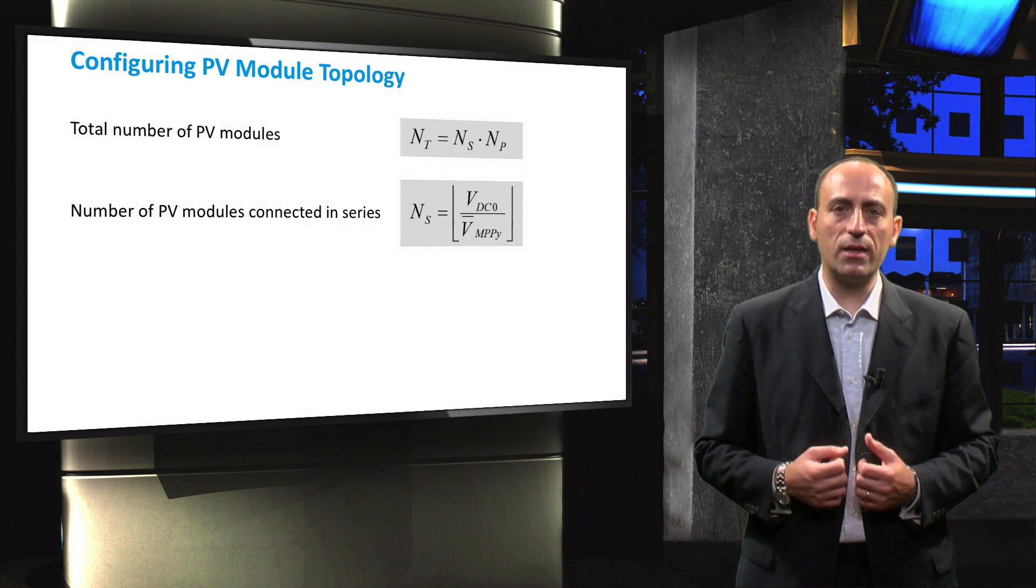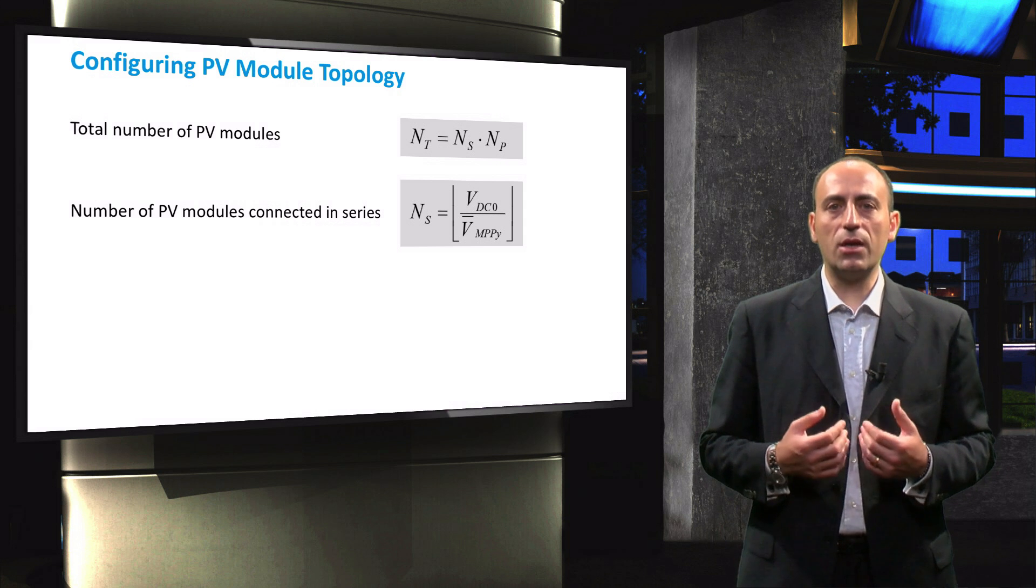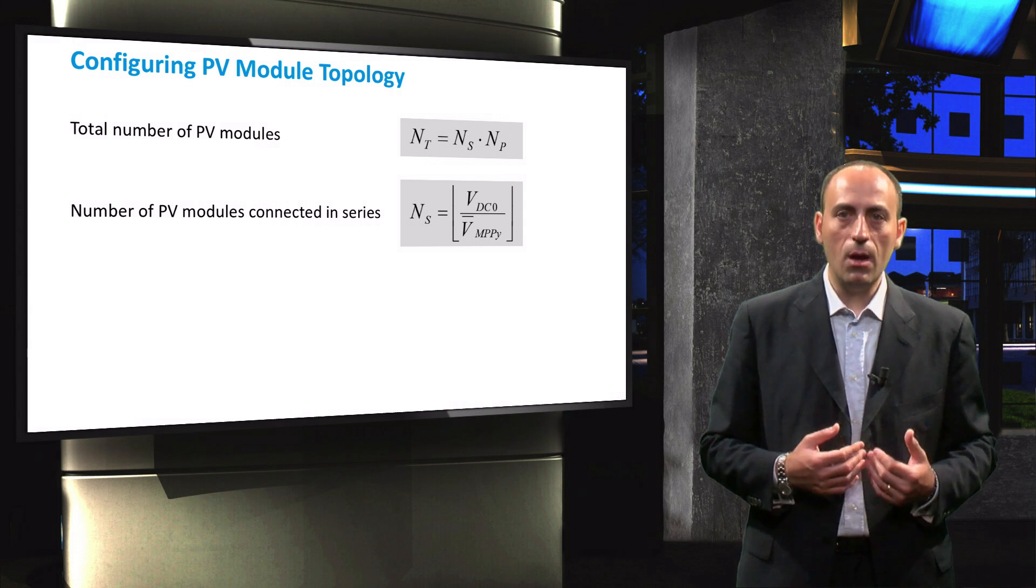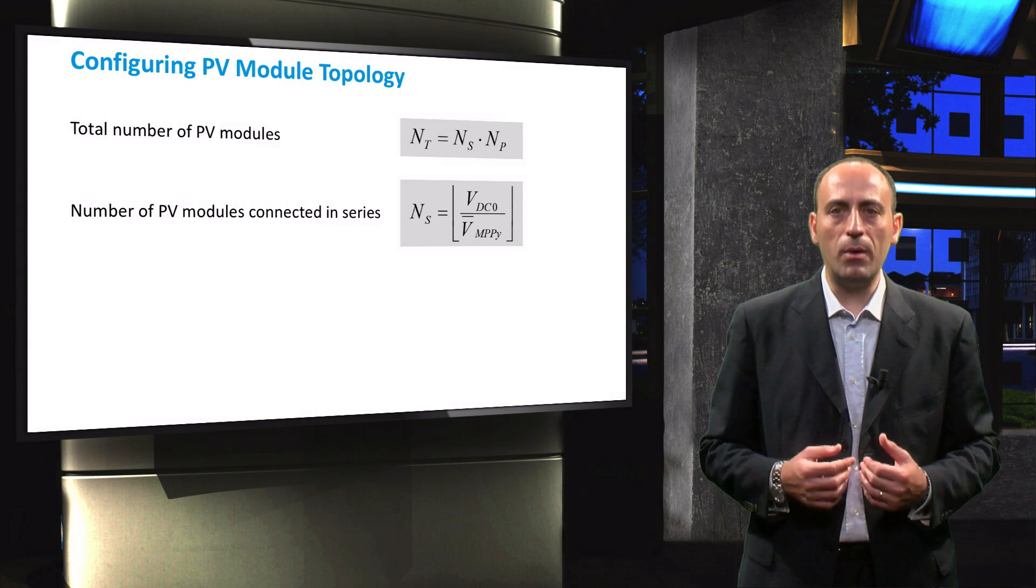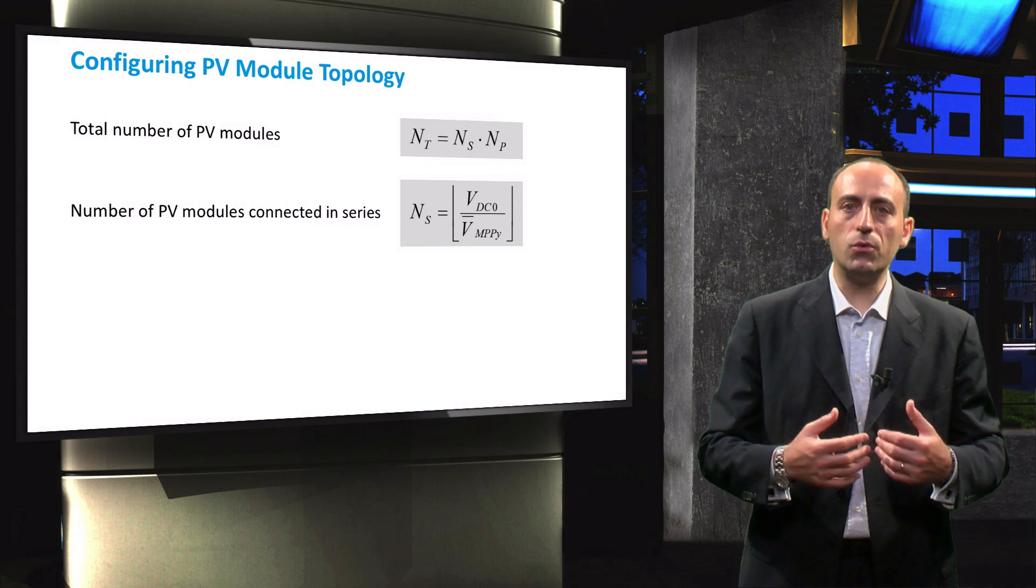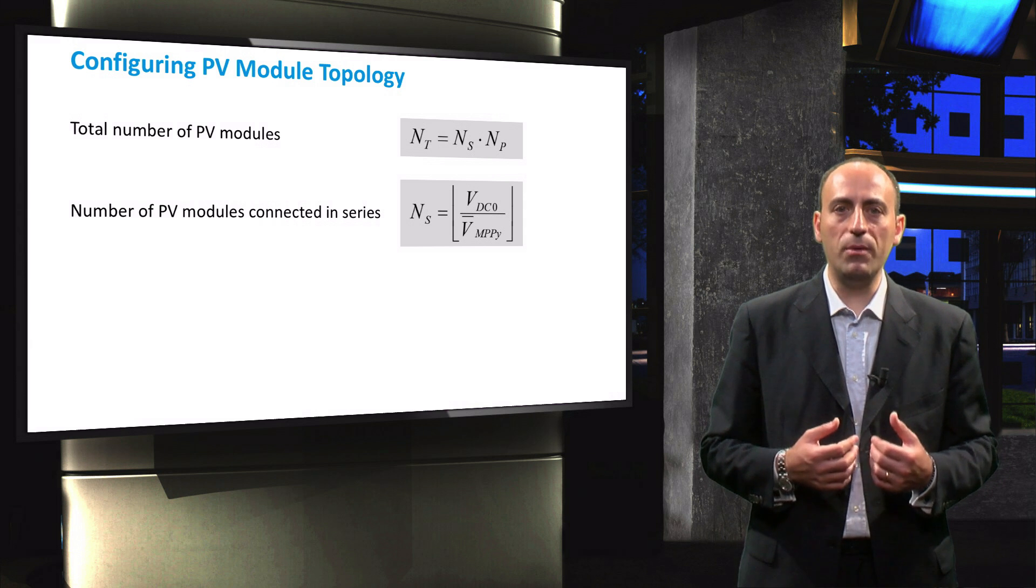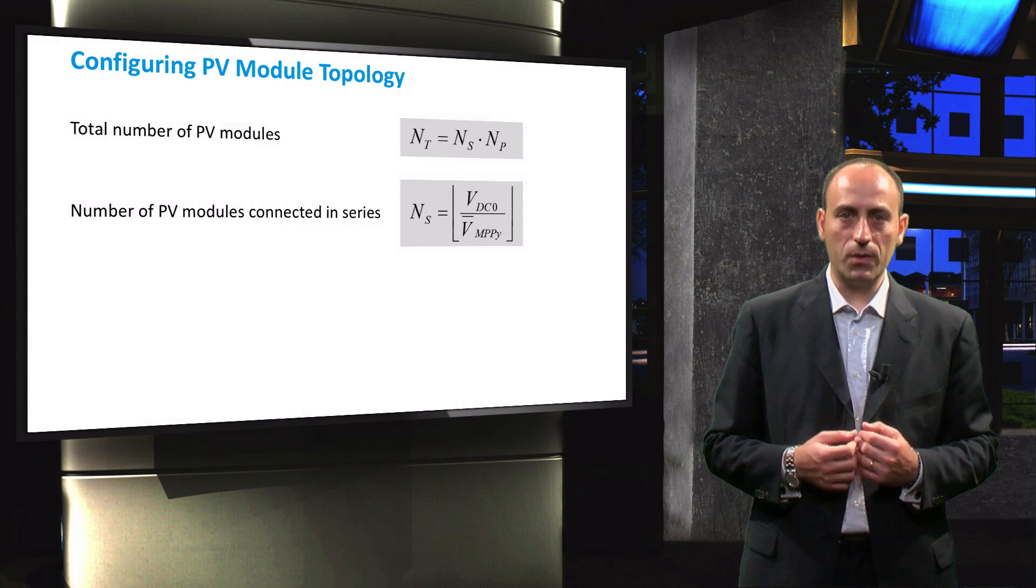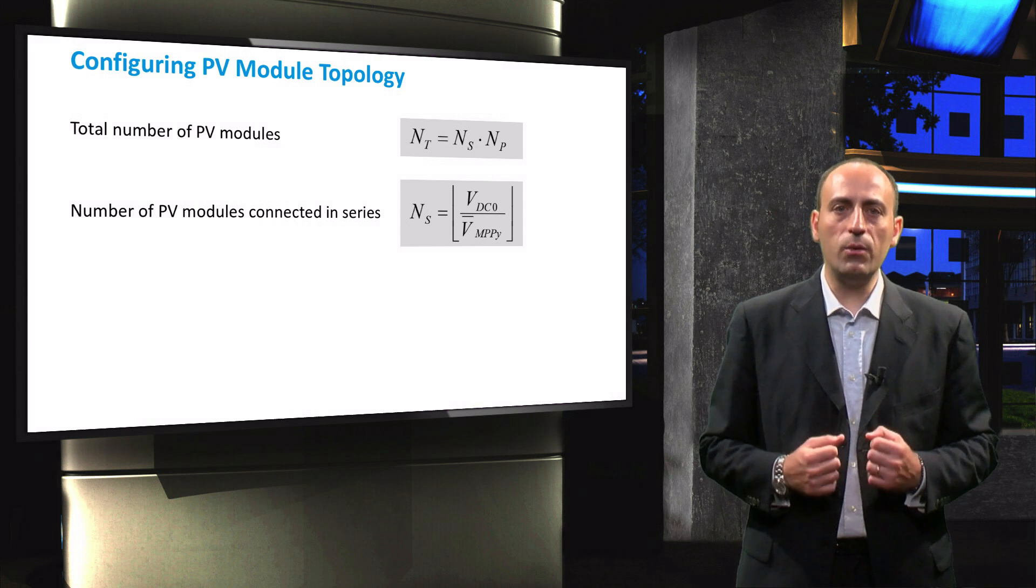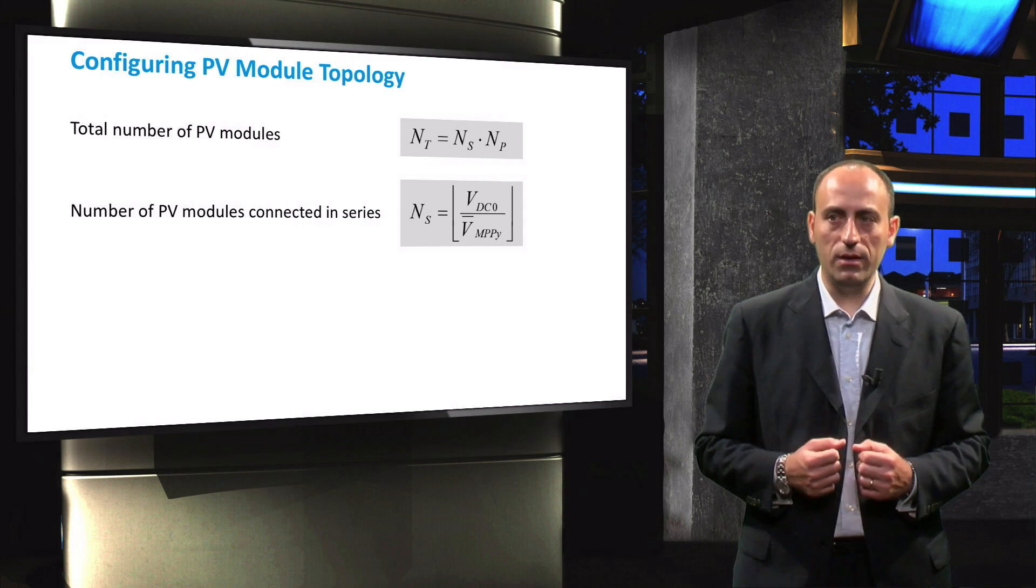The number of series-connected modules, NS, is calculated by dividing the nominal DC voltage of the inverter by the averaged maximum power point voltage of the PV modules. You learned how to calculate this averaged MPP voltage in the previous video. Note that the NS value is obtained by rounding down the calculated value to its nearest integer.